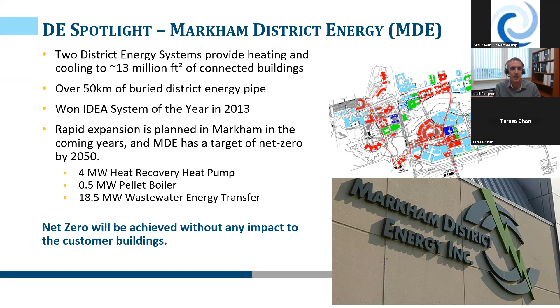The major point to note here is net zero will be achieved without any impact to the customer buildings. This is the benefit of the thermal grid created. By swapping out the heating and cooling generation equipment at the energy center, all these older buildings connected to the district energy system benefit immediately from the decarbonization process back at the central plant. Nothing has to be done in these older buildings, as it's all being done back at the central plant.